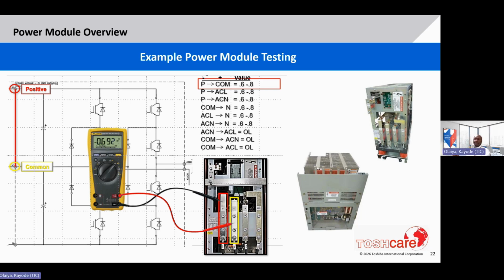You need to connect it to the bus as shown in this picture, following the table for where the positive and negative lead should go. And in this example here, we're measuring between the P and the common, and the value should be between 0.6 and 0.8, which, here it's 0.692. This tells us that the devices between those connections are good. And so you follow that same sequence going down the list and record the values to make sure they match what is expected.